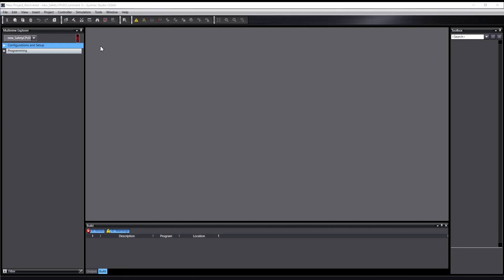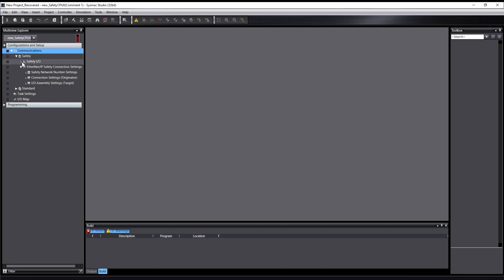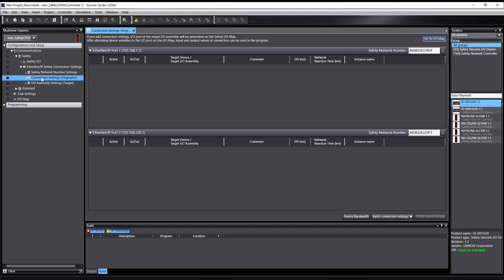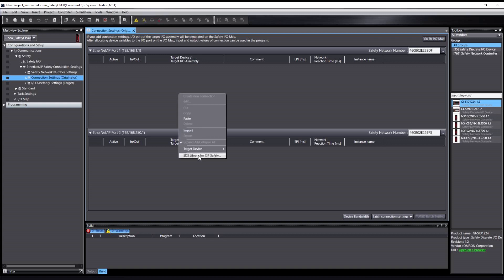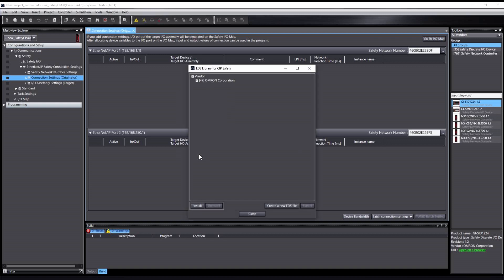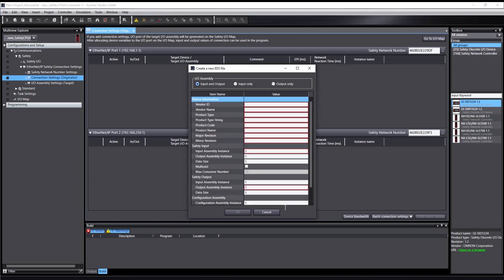Let me show you how to create an example EDS file using this tool in SysMac Studio. First, select the Safety CPU from the Multi View Explorer window and navigate to Connection Settings Originator under Ethernet IP Safety Connection Settings. In the Connection Settings window, right-click under the Ethernet IP port and select EDS Library for CIP safety. Then select New EDS File to open the Parameter window for the new device.